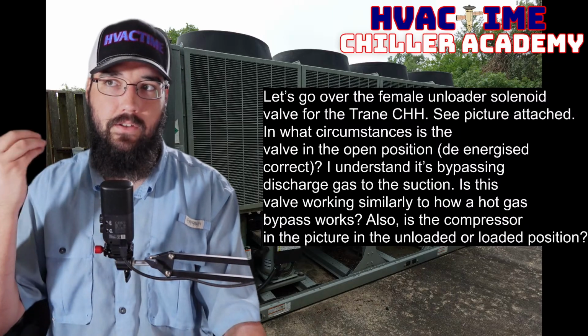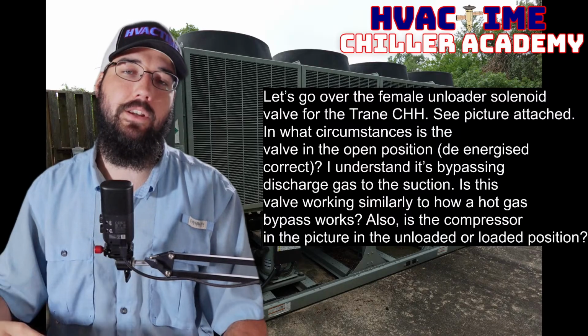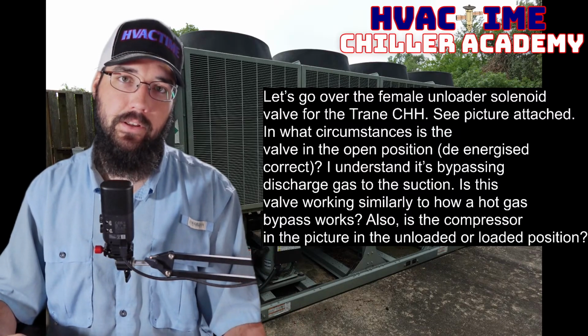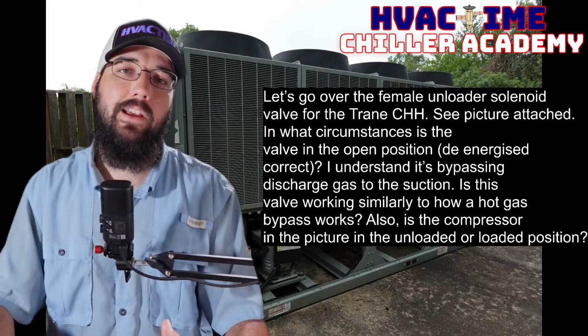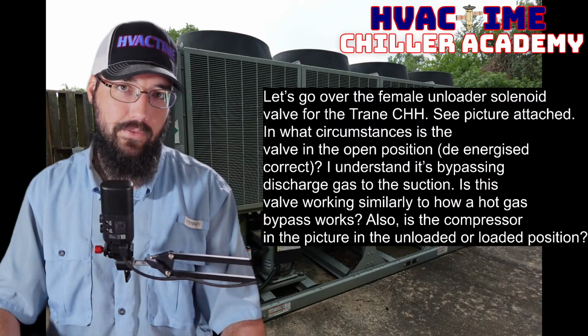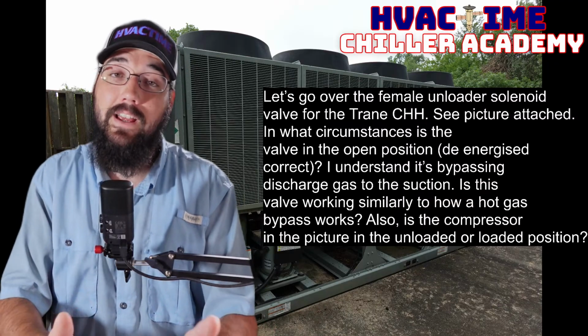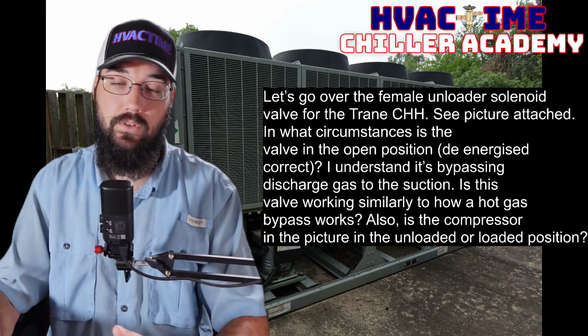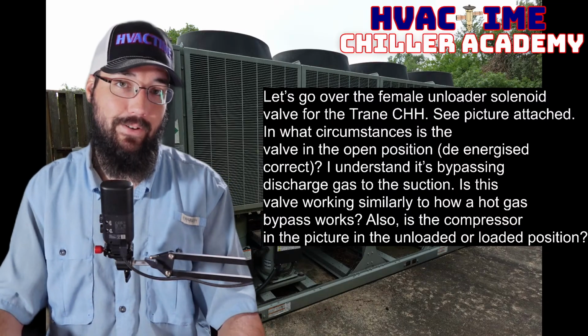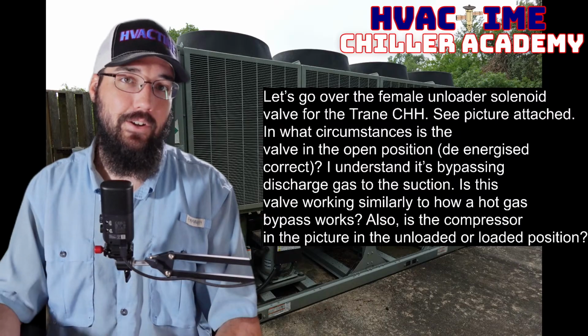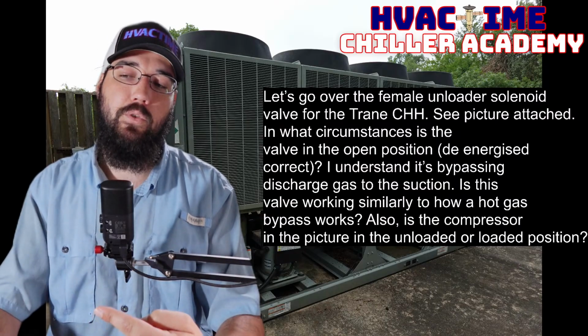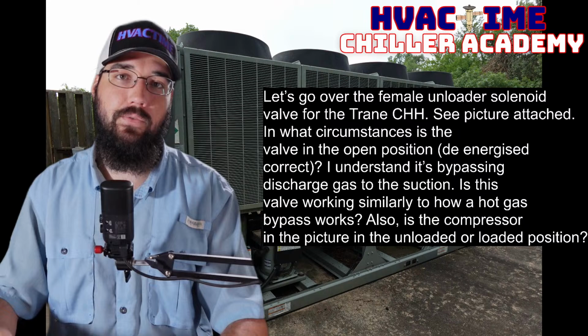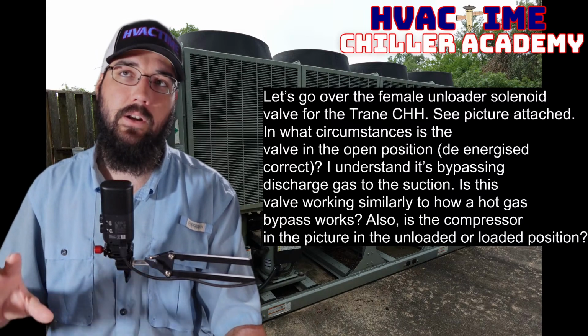And there's a tone difference that you can hear between when the female unloader is engaged and when it's not. Now that takes a trained ear to be able to hear for that and to tell the difference, and it can be really tricky to distinguish that. So even if you have a trained ear, it's not always real quick, but you should be hearing the solenoid's firing sequence as it's going through there.